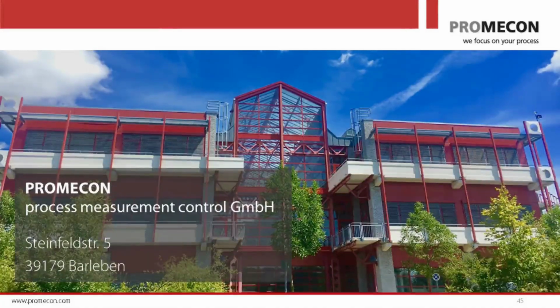We have time for one more question, so we'll just pick one. Are changes of the ductwork necessary for installing the sensors? Okay, another good question. Ductwork. I have not touched upon this so much, but of course, in power stations, ducts are always wide and short. In terms of their length, they always have a huge cross-sectional area. And usually the ducts bend around the corner and then they split, and here's the burner. So you have stratification issues. You don't have much straight run on the duct. So are modifications necessary? On a long duct, no. We just put the sensor in through a couple of openings, and that's it.